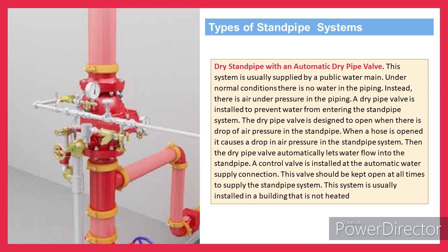The dry pipe valve is designed to open when there is a drop of air pressure in the standpipe. When a hose is opened it causes a drop in air pressure in the standpipe system. Then the dry pipe valve automatically lets water flow into the standpipe. A control valve is installed at the automatic water supply connection. This valve should be kept open at all times to supply the standpipe system. This system is usually installed in a building that is not heated.